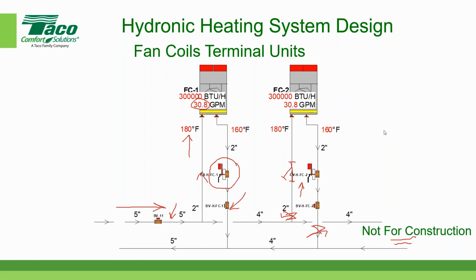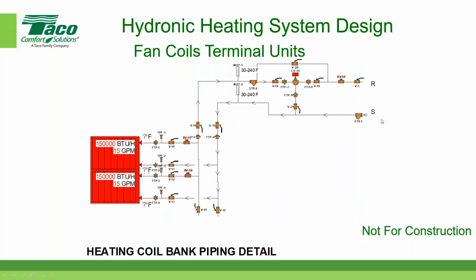And I also have a detail of what you might consider for a terminal device. And again, in this case, we have two coils at 150,000 BTUs each, and you can see all the different piping components. In this configuration, they've shown a three-way valve. Here, you can use either a three-way valve or a two-way valve in your system. Most systems today use two-way valves to take advantage of the variation in the flow as the valves modulate open and close. We have a separate discussion about how that works in terms of control.